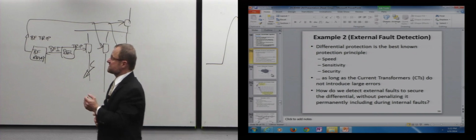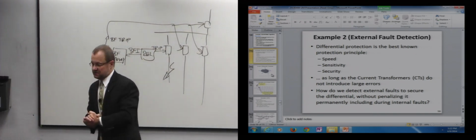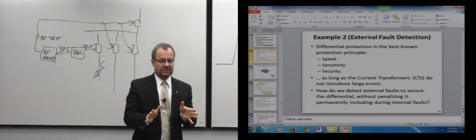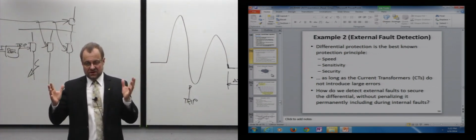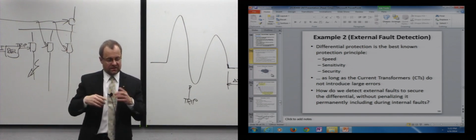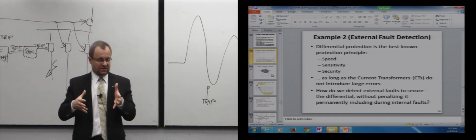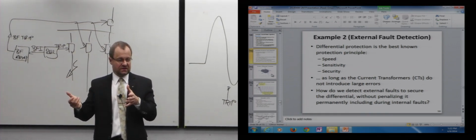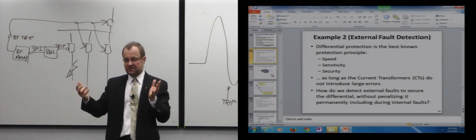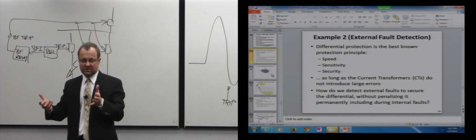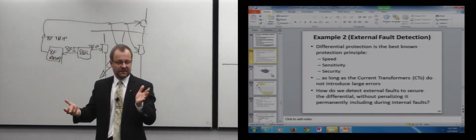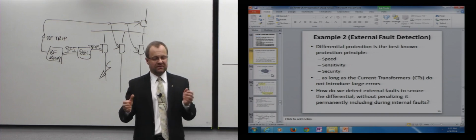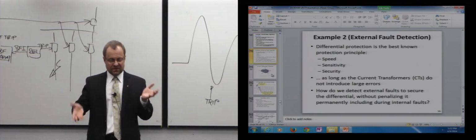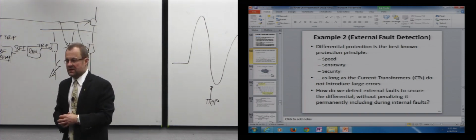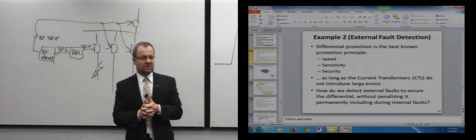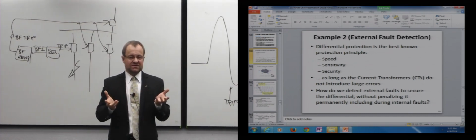So the second example is external fault detection. This is about the differential principle. So you probably learned about the differential principle, right? Kirchhoff's current law says that you sum all the currents around a piece of apparatus and it's zero. If it's not zero, it means that you are not measuring all the branches. So there is an extra branch that was just created, and that's why the current is not zero. That extra branch is the fault, right? So if the current is zero, it's healthy. If the current is not zero, something is leaking. There is a branch created. It's a fault. We have to trip. Works like a charm. The strongest principle we have, except that we don't measure the currents.